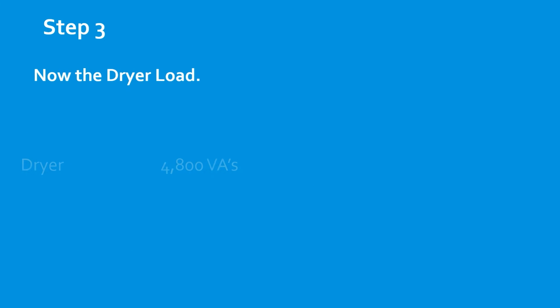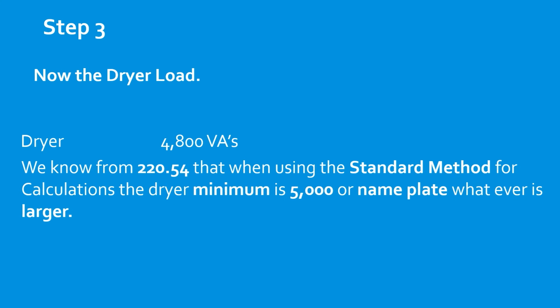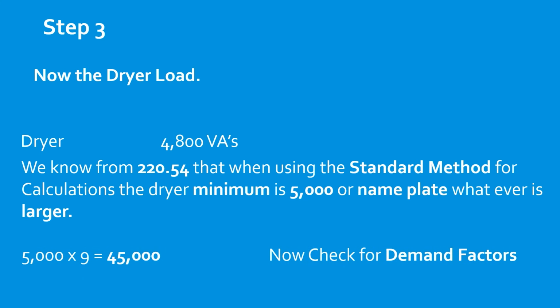Now let's do the dryer load. Okay, our dryers are 4,800 VAs. We know from 220.54 that we must use a 5,000 minimum. So we take 5,000, multiply it by our 9 apartment units, and we're going to get 45,000 VAs. Now we need to check for demand factors. We head to table 220.54, and we see that the demand factor is 55%. So we take our total VAs, multiply it by 0.55, and that is going to give us a reduced load of 24,750.